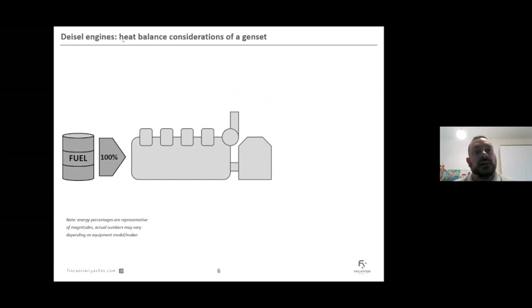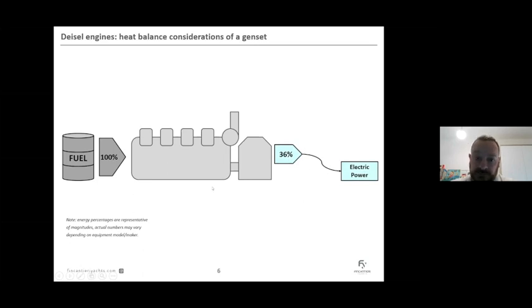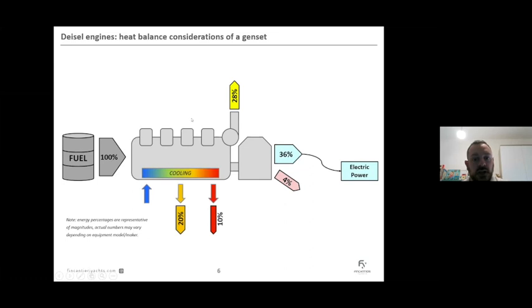Let's consider the heat and energy balance of a genset. We put fuel in, and let's say this fuel has 100% of the energy. This is a generator, so we produce electrical power, let's say 36%. These numbers vary depending on engine model and maker, so consider them as a magnitude, not strict figures. Of that 100%, about 4% is lost as alternator inefficiency, about 28% is lost as hot exhaust gases, about 30% is lost in the engine's cooling loops, both low and high temperature if two loops are available, or 30% in a single loop, and about 2% is lost as thermal radiation inside the engine room.